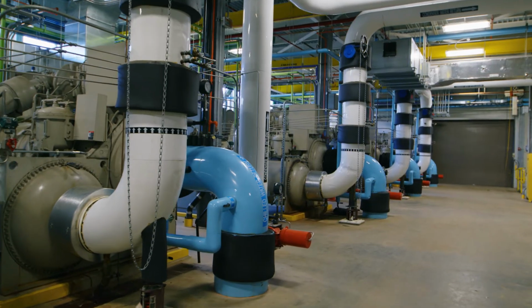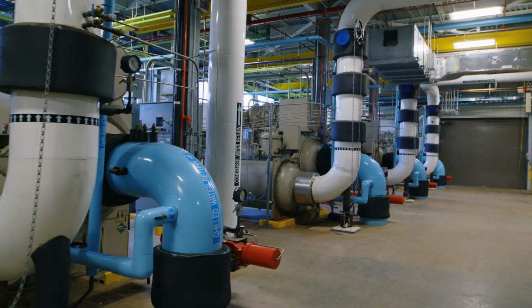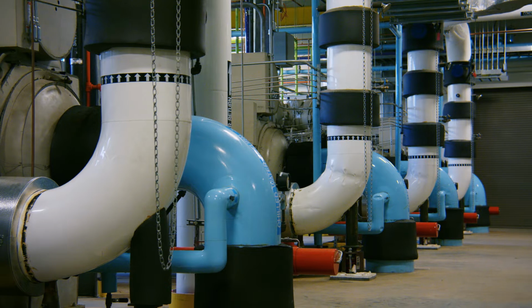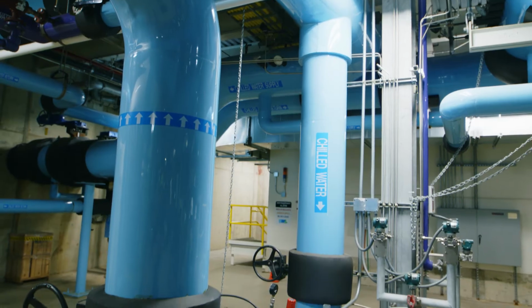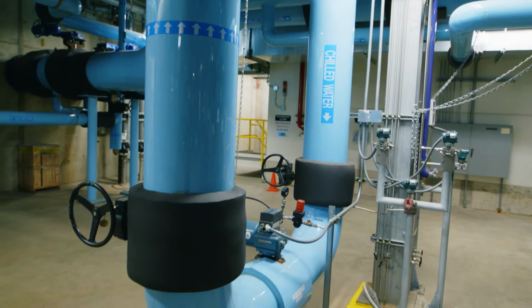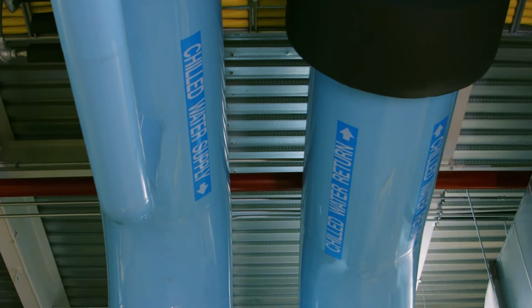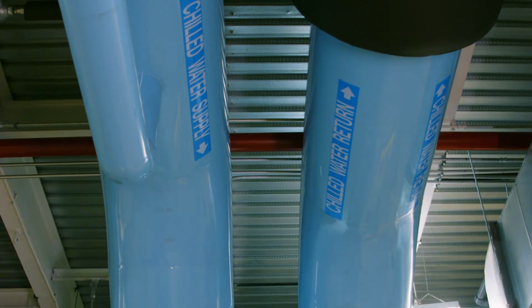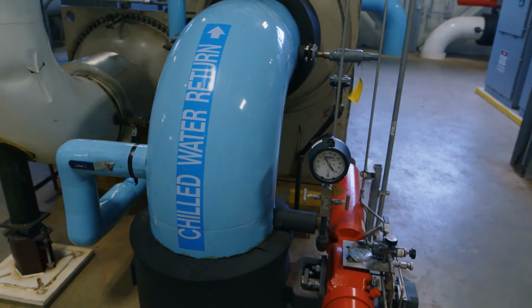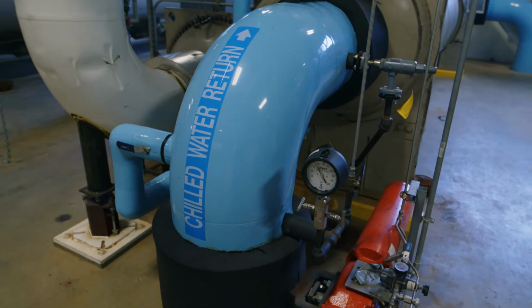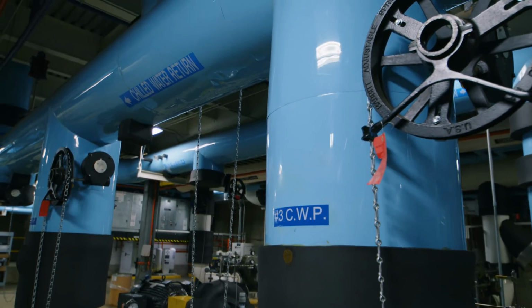At Peffley, this is a highly automated process that takes place in this state-of-the-art facility. The plant operates on a closed-loop system, sending chilled 42-degree water throughout downtown and back. The chilled water then returns as warm 52-degree water in these sky blue pipes.